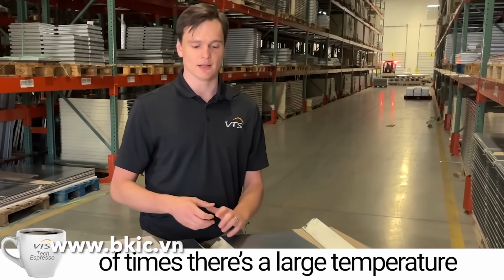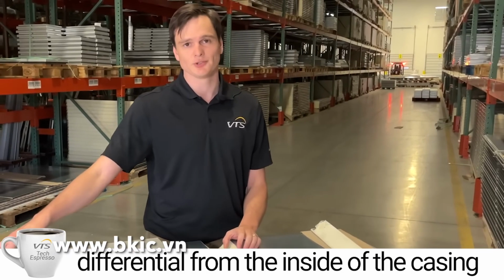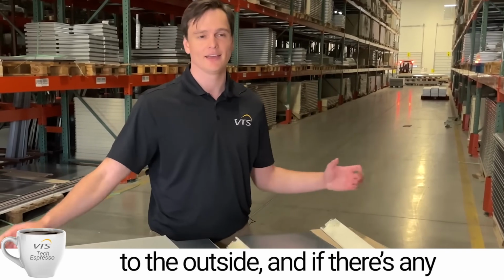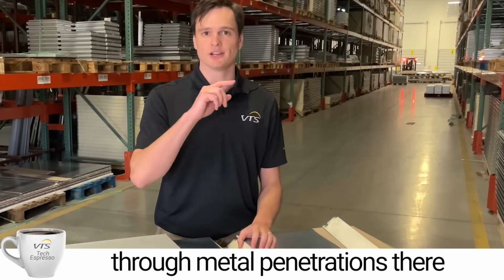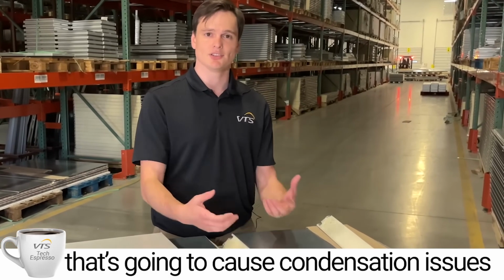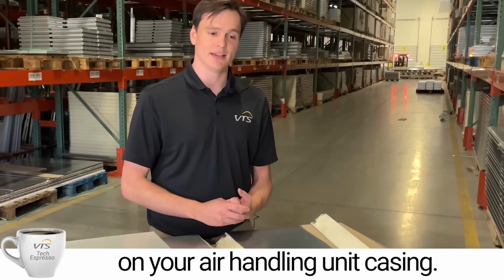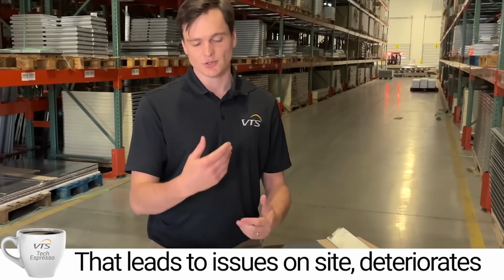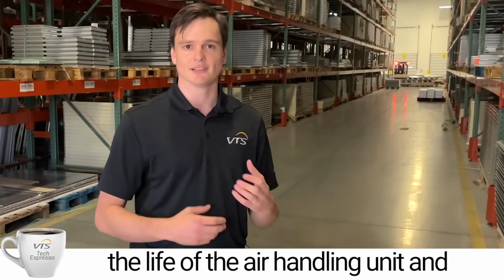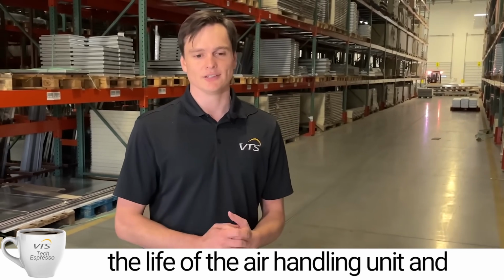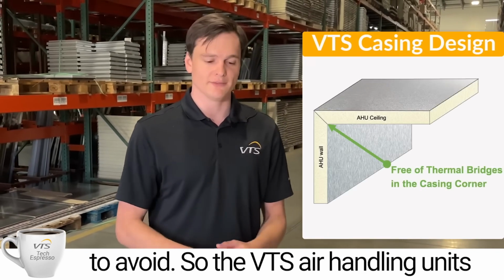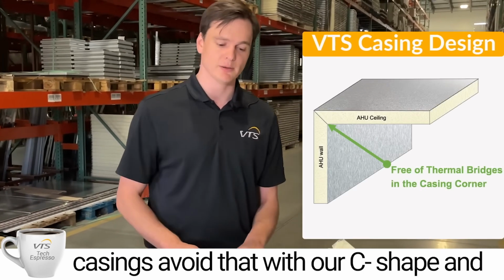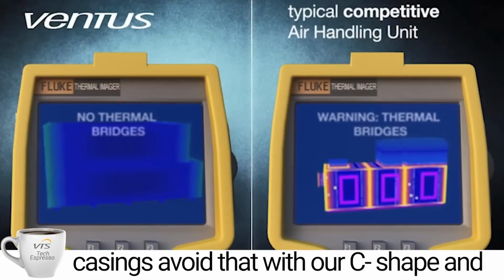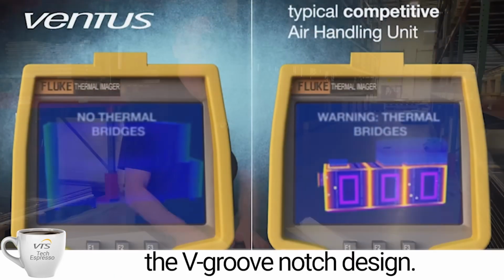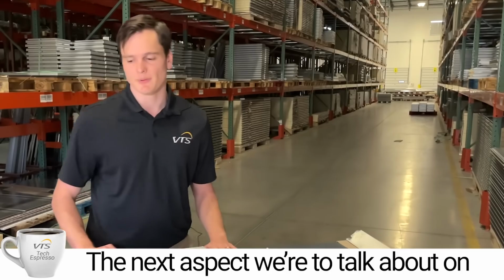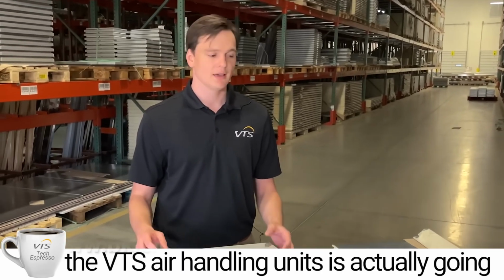A lot of times there's a large temperature differential from the inside of the casing to the outside, and if there's any kind of through metal penetrations there, that's going to cause condensation issues on your air handling unit casing. And that leads to issues on site, deteriorates the life of the air handling unit, and is just generally something you want to avoid. So with the VTS air handling unit casings, we completely avoid that with our C-shape and V-groove notch design.